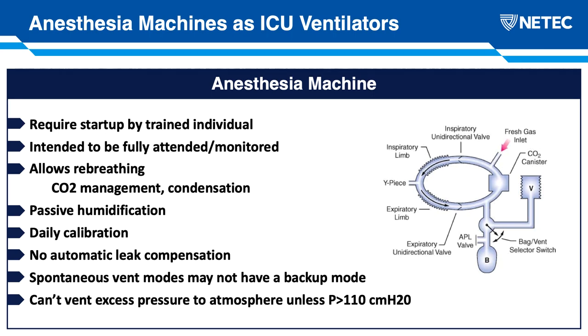Another difference in anesthesia machines as compared to our ICU ventilators is that they require daily calibration. Now, this really takes on a number of different flavors depending on the specific manufacturer of an anesthesia machine. But it's important to note, at least with some of the manufacturers, that if this 24-hour check isn't completed, then some of the compliance data that is taken when you first start up the machine, that makes the measurement of your tidal volumes and thus your minute ventilation accurate, past 24 hours, if you were to temporarily pause ventilation, that compliance data is lost, and the accuracy of those measured volumes would then go down.